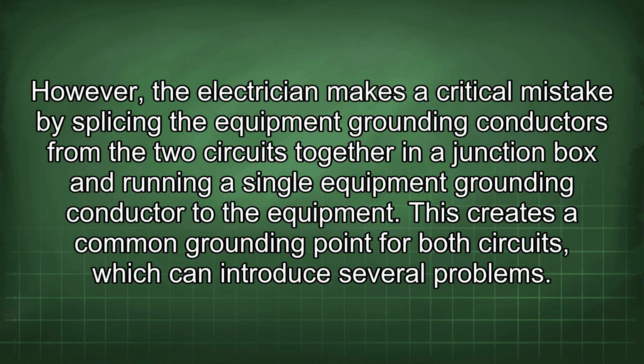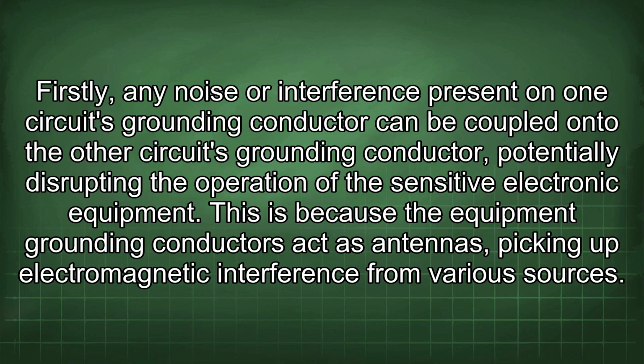However, the electrician makes a critical mistake by splicing the equipment grounding conductors from the two circuits together in a junction box and running a single equipment grounding conductor to the equipment. This creates a common grounding point for both circuits, which can introduce several problems. Firstly, any noise or interference present on one circuit's grounding conductor can be coupled onto the other circuit's grounding conductor, potentially disrupting the operation of the sensitive electronic equipment.